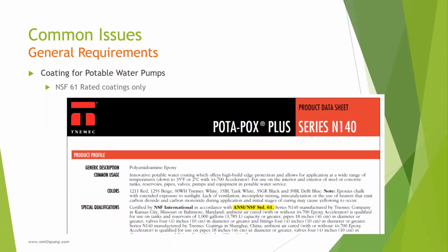And even coatings are NSF approved. We always recommend using an NSF rated coating when using a potable water pump. The Tnemec data sheet here shows their N140 epoxy system is NSF 61 certified.